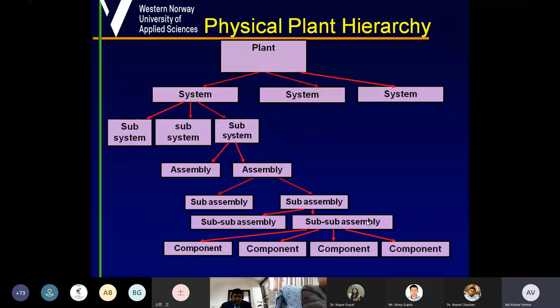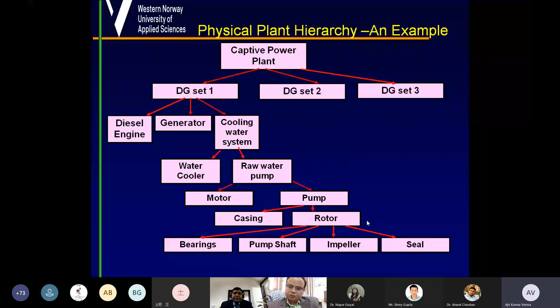So for example, a captive power plant with 3 diesel generator sets, maybe say a call center where you require that the power should be available, high availability. So you have multiple diesel generator sets. DG sets basically would constitute our subsystems like diesel engine, generator, cooling water system. And we expand a part of this tree, cooling water system. Then you have the water cooler, then you have the raw water pump, then the motor, the pump, the casing, the rotor, bearings, pump shaft, impeller, and seal at the component level.